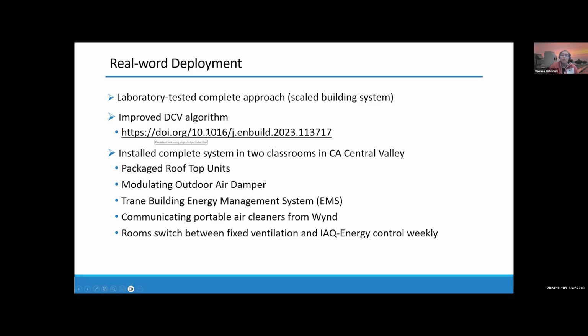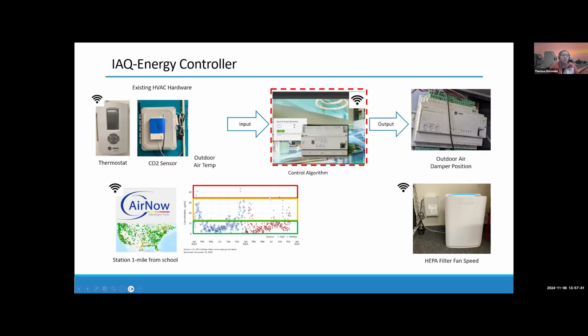We also need to be able to do demand control ventilation. We need to be able to track a CO2 set point. Historically, those algorithms don't work very well. We have demonstrated a proportional integral feedback algorithm for DCV that works extremely well in most building types, and that's published. And so I'll share the link to that as well. And then we've now taken this complete system and it's been operating for the last year in 2 classrooms in California's Central Valley. And my last slide here, I'll just show a quick diagram of that.